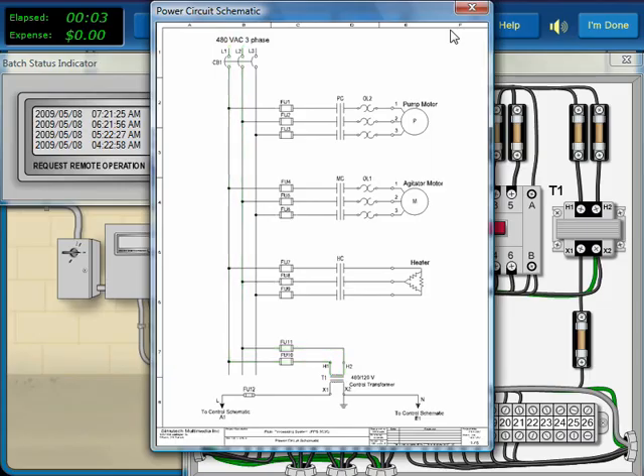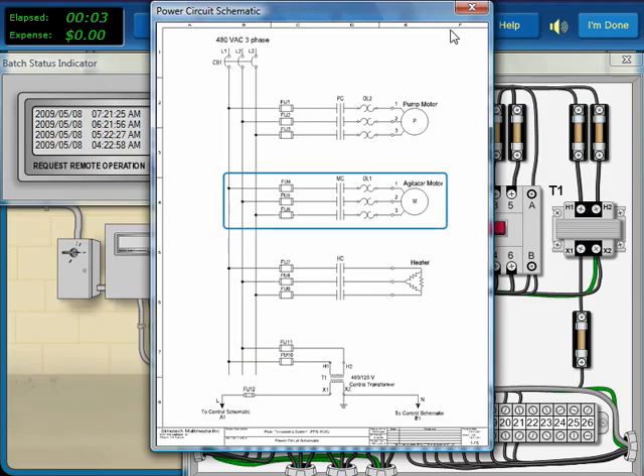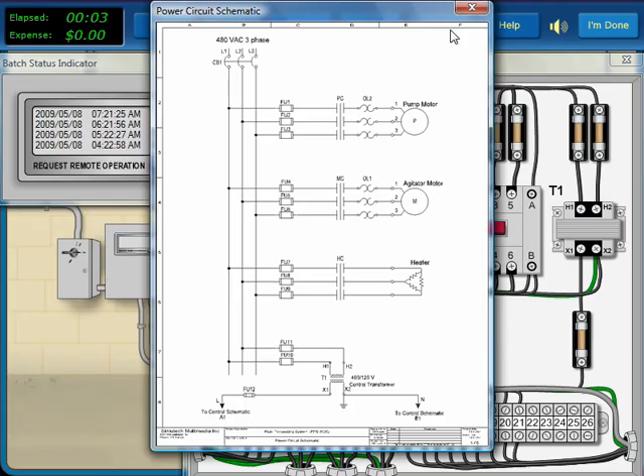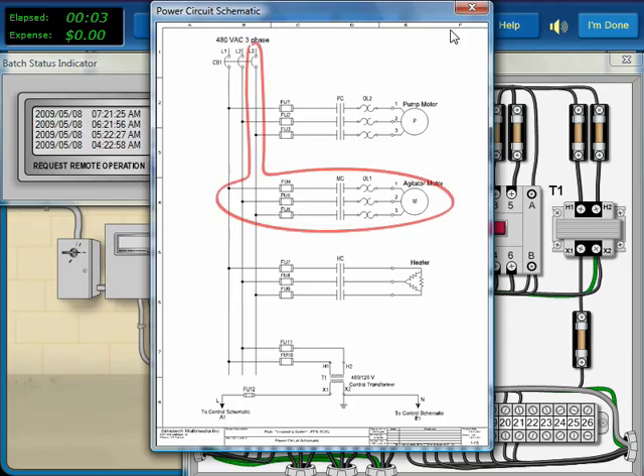Also, since the overload trips, we know that there is current in at least one phase of the agitator circuit. Therefore, the problem area is confined to the agitator power circuit and the third supply phase.